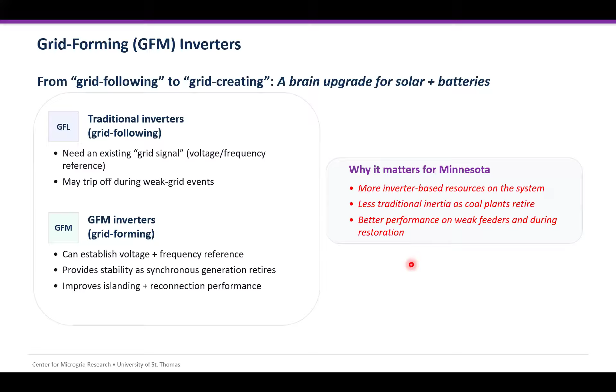the reconnection performance as well. So why does this grid forming inverter matter to Minnesota? Because we now have more inverter-based resources in the system due to the expansion in wind and solar energy, and we are retiring the coal plants, so we have less inertia and a weaker grid. The grid forming inverter gives better performance on weak feeders and during restorations.